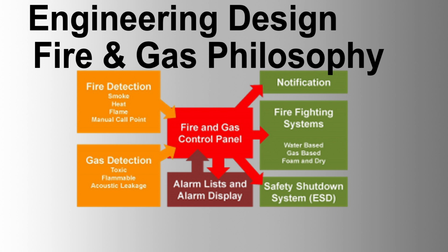Maintenance override. Maintenance override functions bypass predefined field fire and gas devices for maintenance activities. DCS soft maintenance override switches, MOS, should be latched with operators alerted after a set duration. Fire and gas activations should be indicated in graphics, and activation push buttons should be pulse type.